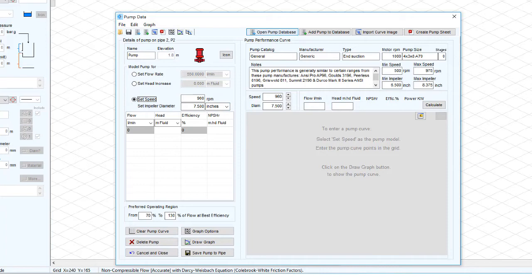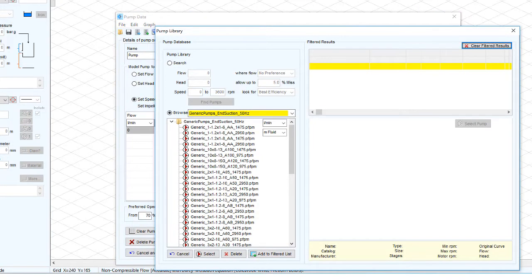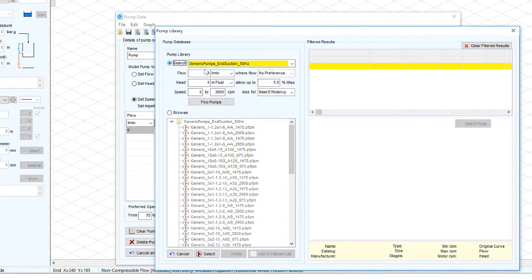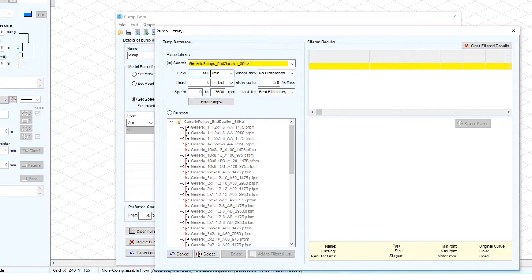Now click open pump database. The pump database can be used to search for pumps that match a set of specific criteria which include flow and head requirements previously calculated within a given speed range.